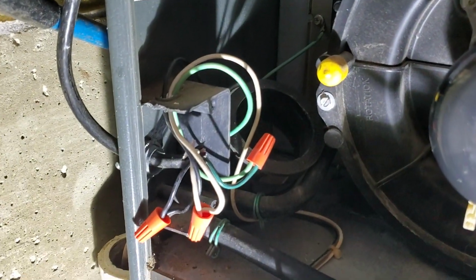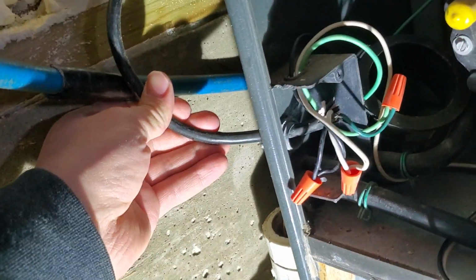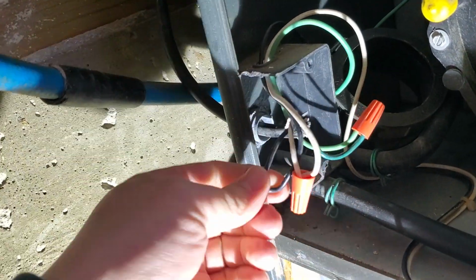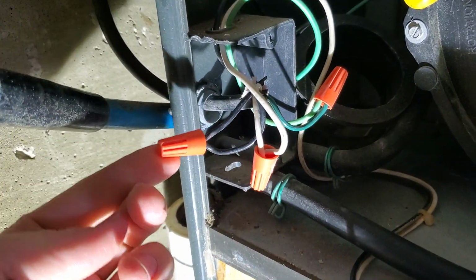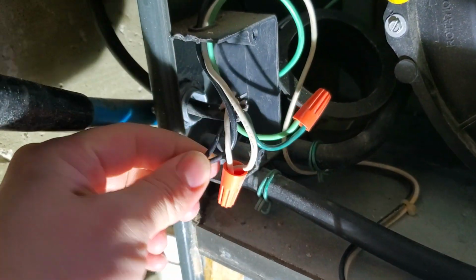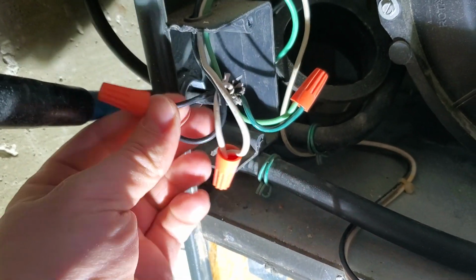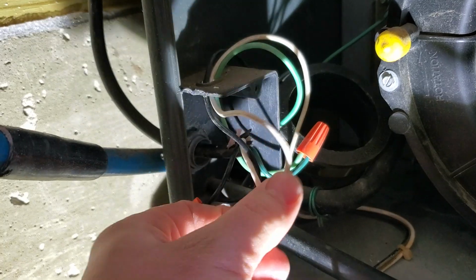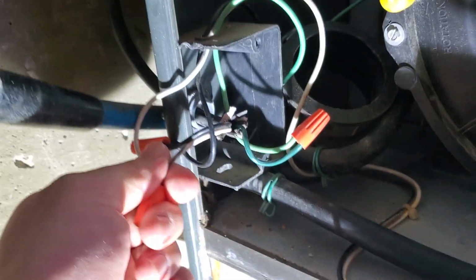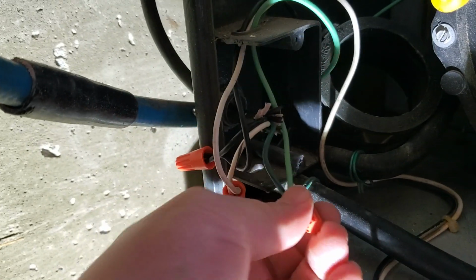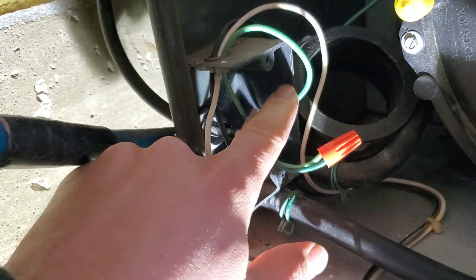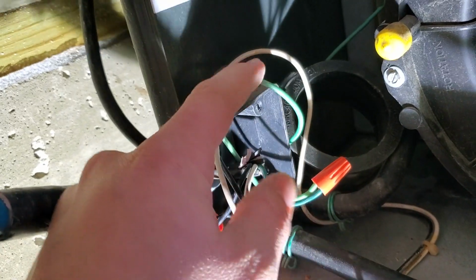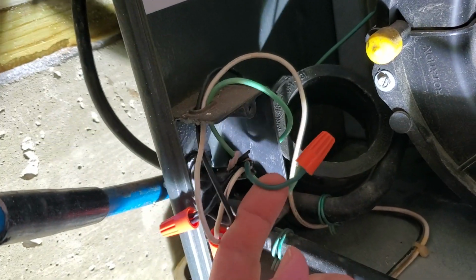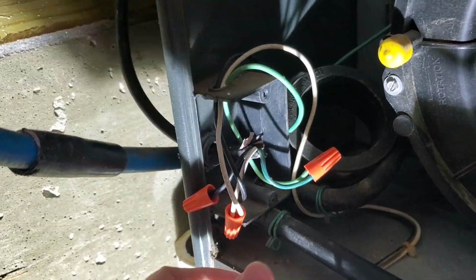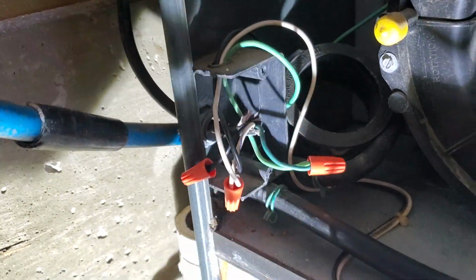Okay, so right here is the wire that comes in from that drop cord. Comes through the side of the furnace, and then we have just 3 connections. We have our 110 volt line voltage. This is the hot wire that comes in, so that's just connected up to the color that feeds the furnace. Same thing for the neutral, white wires connected together, and the ground wire connected right here. Some furnaces will have just a grounding screw attached onto the frame, so if you don't have a green wire, it probably means that you're supposed to take that ground wire and land it directly on the cabinet inside of that box. But in this case we do have a wire that we just connected onto.